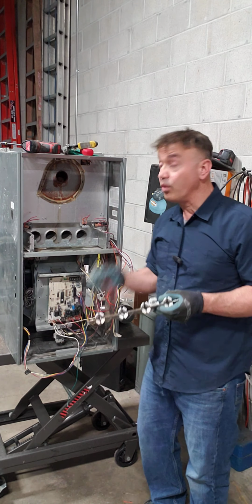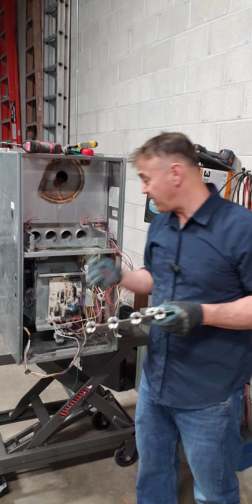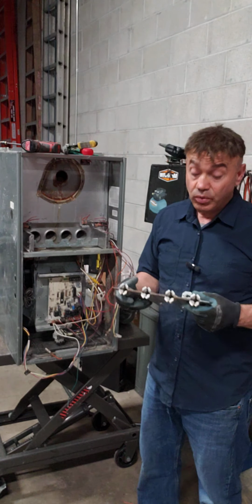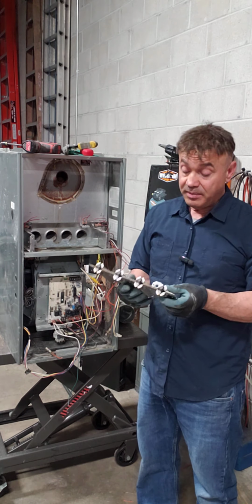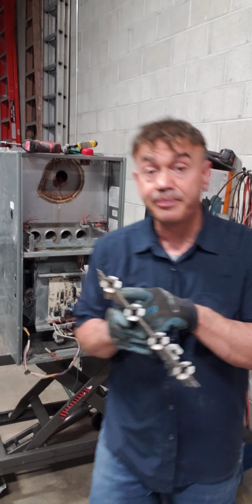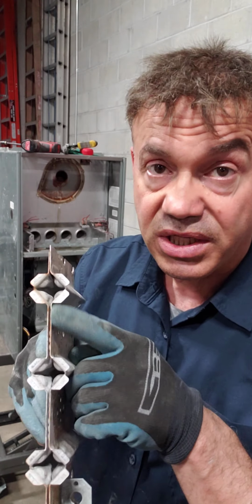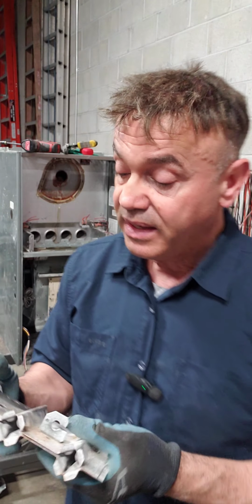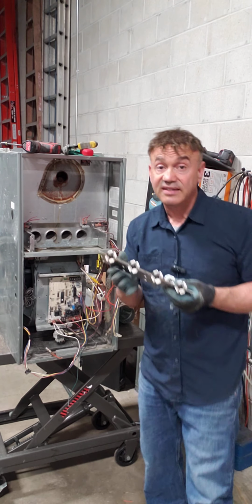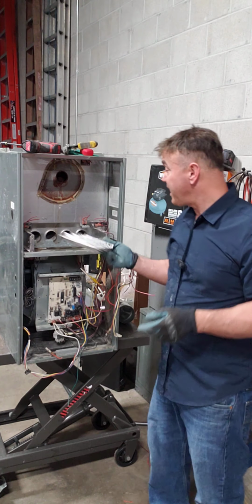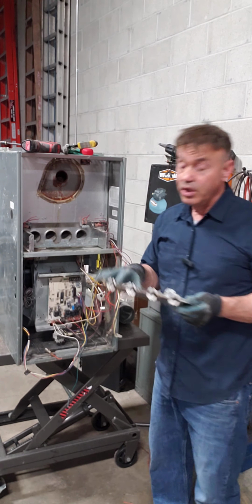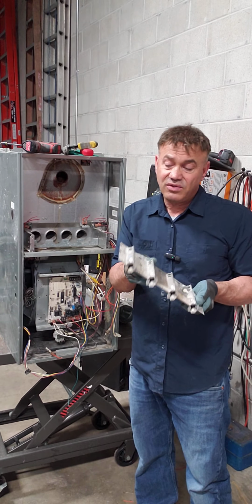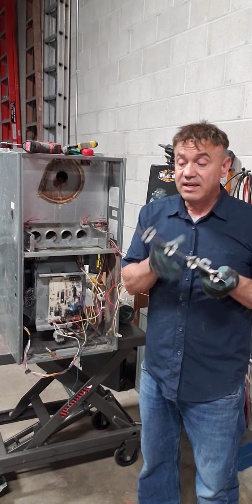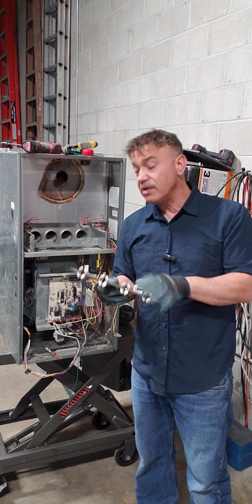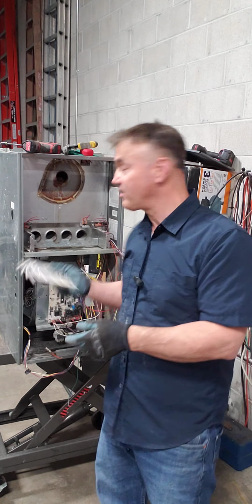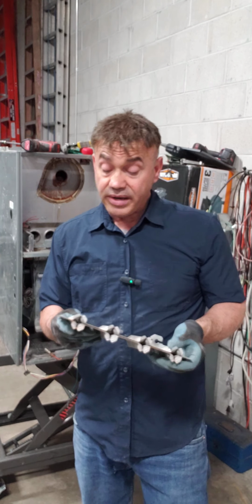to the flame sensor. One case of a bad flame sensor, which I keep telling you because I learned the hard way, could be that this gas pathway is plugged and dirty. So it might light this one, and this one it doesn't light. If you can see it like this, if you're lucky enough, this has to be cleaned. Usually we go like this, or use CO2 with pressured air. Sometimes that doesn't work. We still have to take this off and brush it with a wire brush.